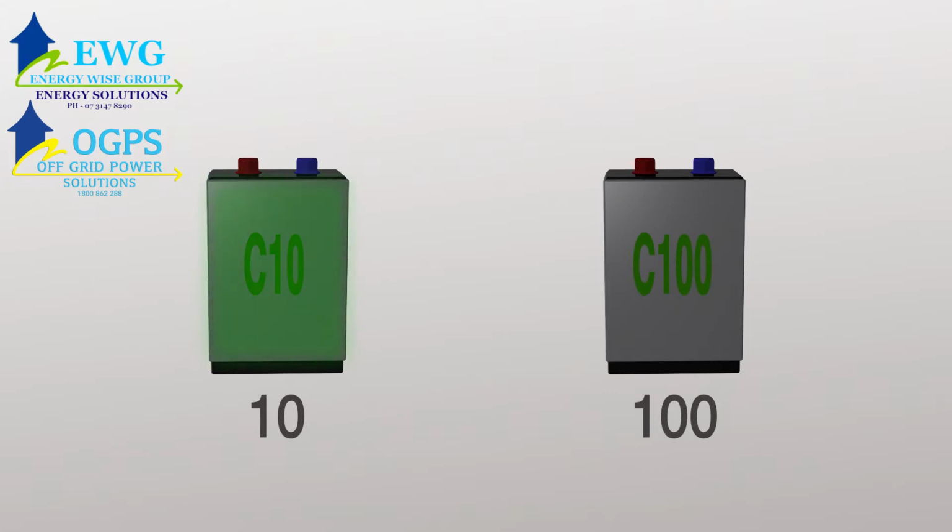Most modern sites should be calculated at the C10. It is generally expected that the energy will be available over this period. Commercial communication sites or UPS units will have slightly different C rating needs.